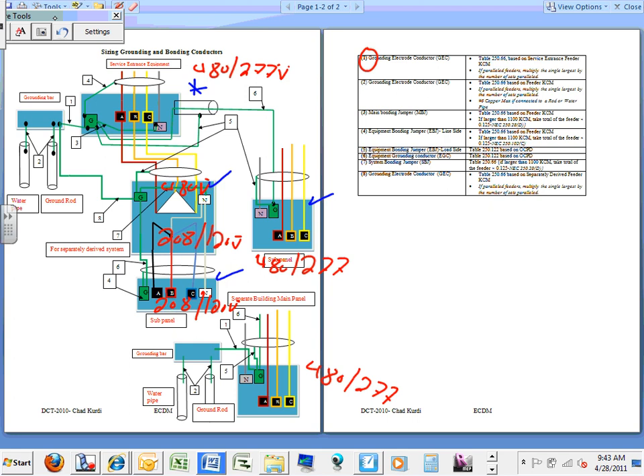Done. So Spencer, if I give you the amps right now and I ask you to size this service, for anything number one, can you guys see where number one is? Number one is right here, this conductor. Everybody can see the conductor going from the ground bar in the switchgear to the ground bar on the wall. When we were at Cummins yesterday, guys, do you remember when Tim pointed to that ground bar on the wall and said the generators are all grounded, bonded to that ground bar right at the top? It was just a little bit below the structural ceiling. I don't know if you remember that. So number one is my grounding electrode conductor. Wherever you see number one, that is my grounding electrode conductor.